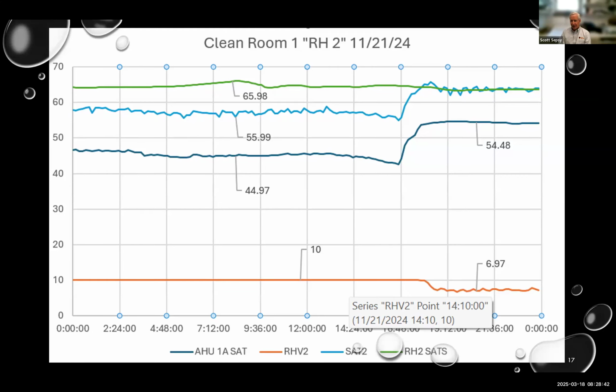So this is a trend of a particular coil over a longer stretch of time here. The red is the voltage to the valve, and you can see here at 10 volts, the set point, which is green, was not made. The light blue was the actual discharge temperature, and it couldn't make it. The darker blue is the incoming air temperature to the coil. So even at 10 volts, it couldn't make the set point. What you really want to see here is an orange line that's below 10 volts, and you want to see the light blue line over the green line all the time. And that means it's working correctly.